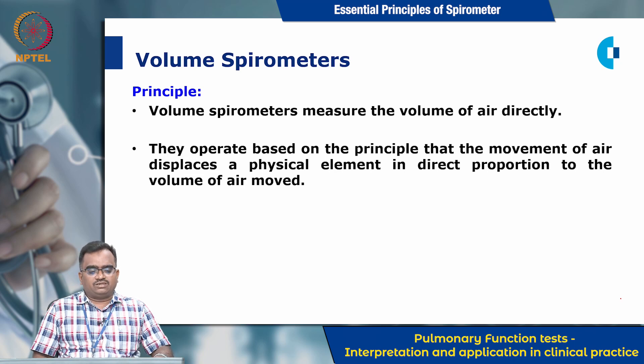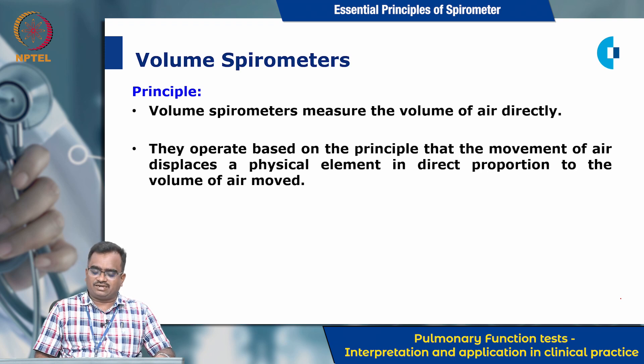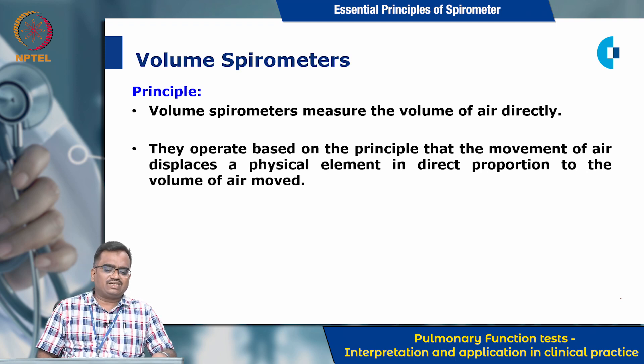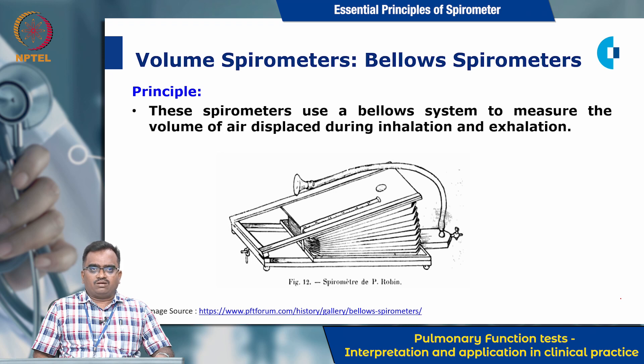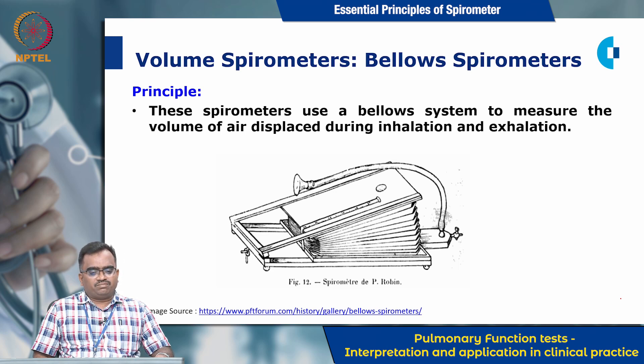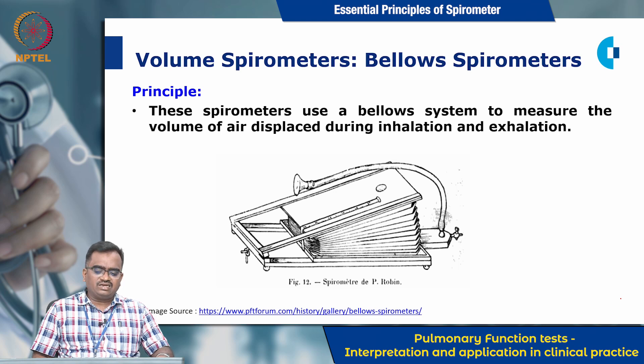Volume spirometers: as the name indicates, they measure the volume of air directly. They operate based on the principle that the movement of air displaces a physical element in direct proportion to the volume of air moved. Among various volume spirometers, number one is the bellows spirometer, which is based on the principle of a bellows system to measure the volume of air displaced during inhalation and exhalation.